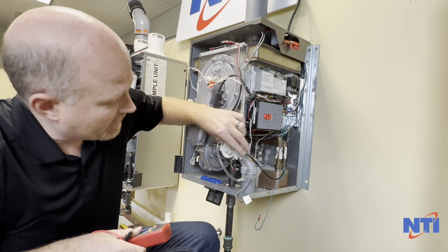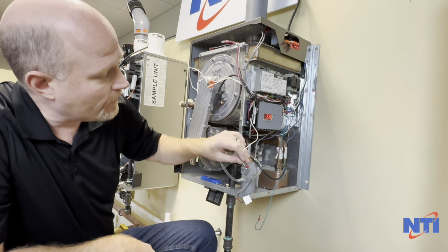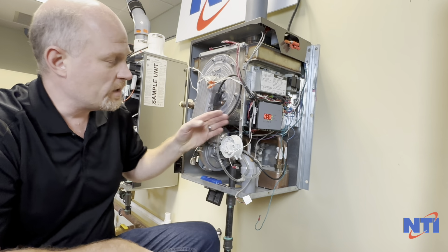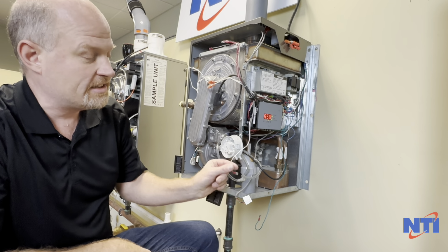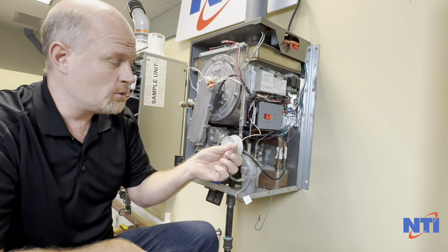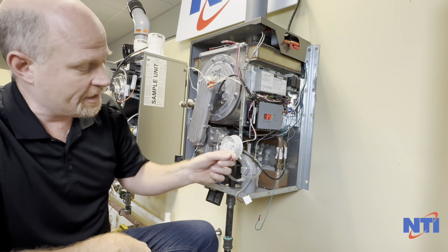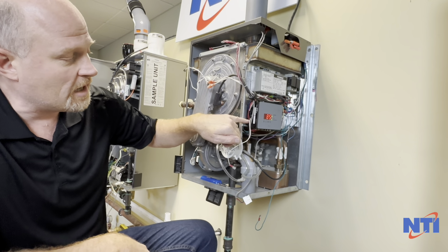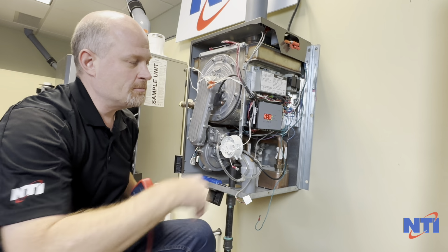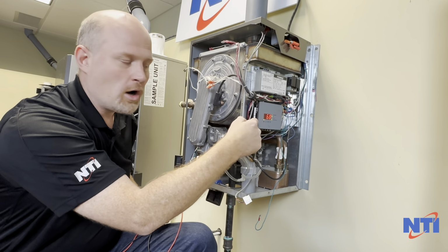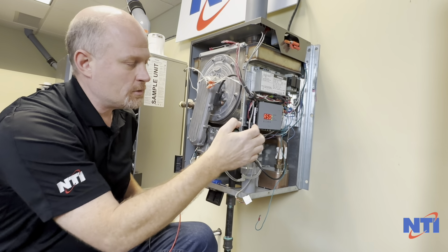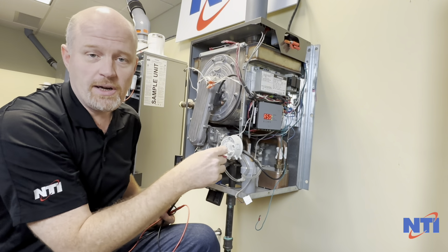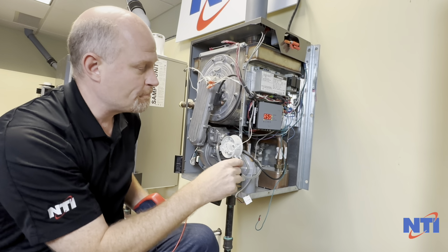You may also notice that because I've unplugged this wire, the Sentry control has gone to an ASO code. What that means is if this wire is disconnected, you should always get an ASO. If you don't, and you're still getting an ASC with this wire removed, this is the white wire from the air switch, it goes to pin 5 here. That means that there's some damage to the Sentry control, so possibly water or something is shorting this out. If it still says ASC and this wire's off like I have it here, you actually do have a bad Sentry control and need to replace that.